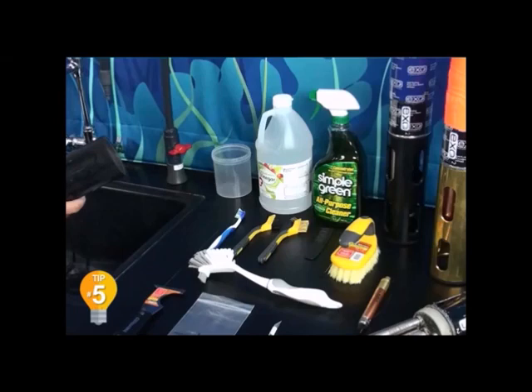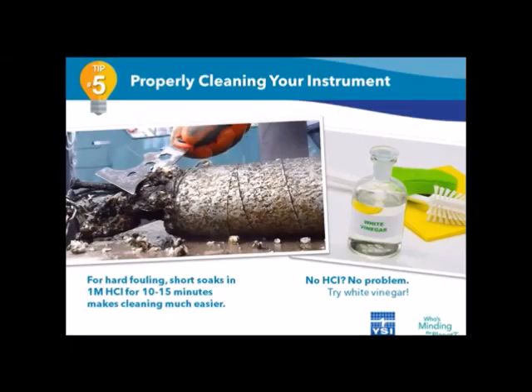So for most of my deployments, soap and elbow grease can typically remove most soft fouling. Soft fouling would include things like silts and worms. I like to use a brush to get the bulk of the cleaning off, and then I clean each sensor more thoroughly with a scouring pad.